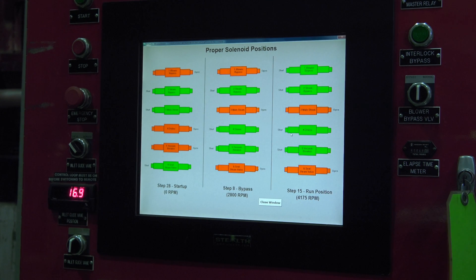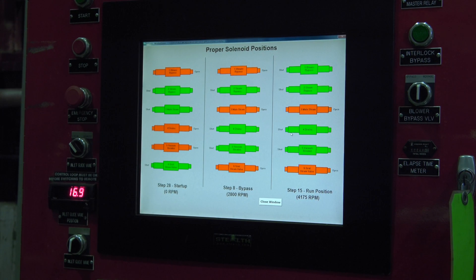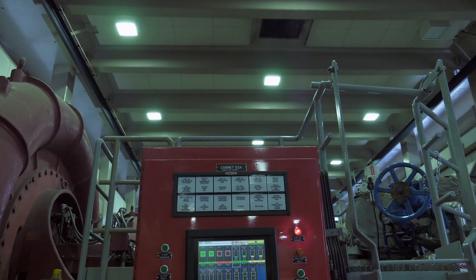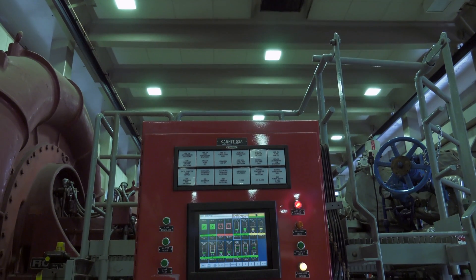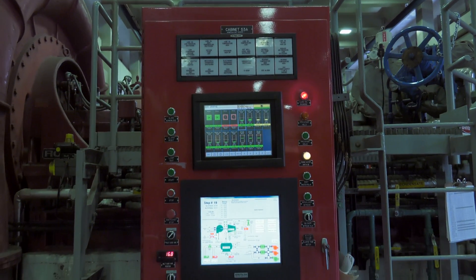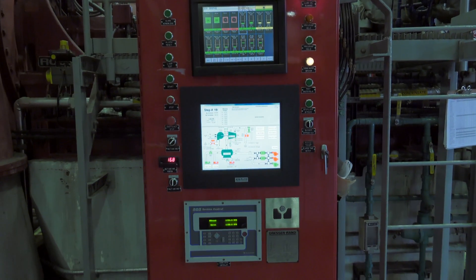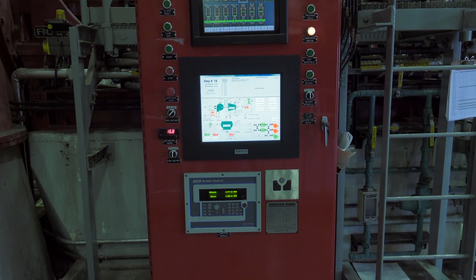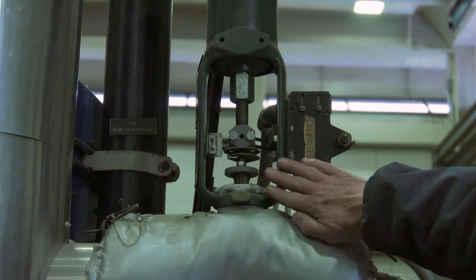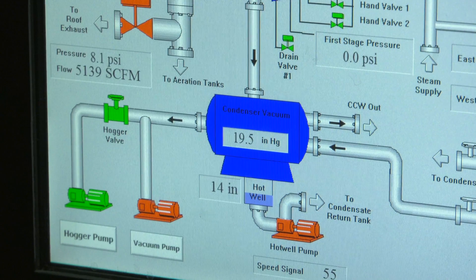To start the aeration turbine, a series of events must occur in sequence and with proper timing. The sequence and timing are coordinated by a PLC located in the red control panel of each turbine. During each step of the startup sequence, the PLC opens valves and drains such as the steam bypass valves and checks for satisfactory performance such as proper condenser vacuum.